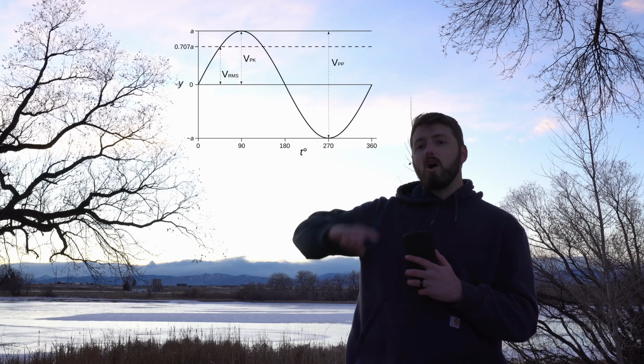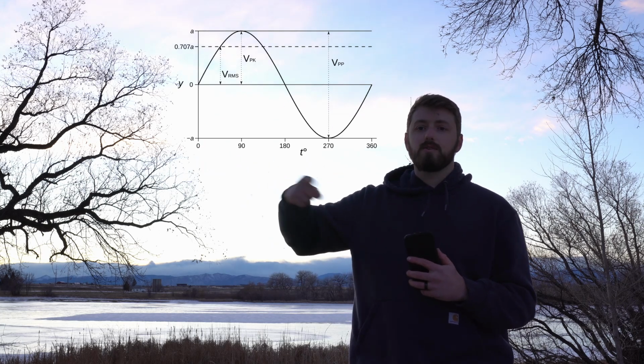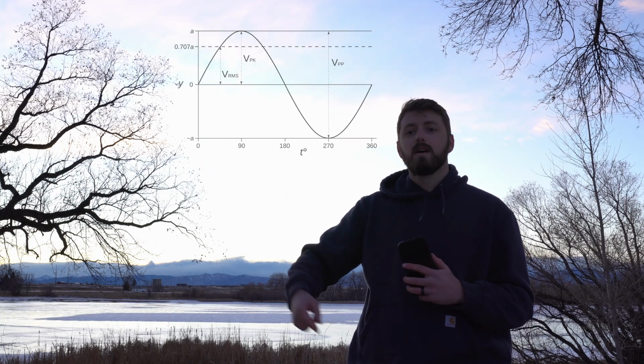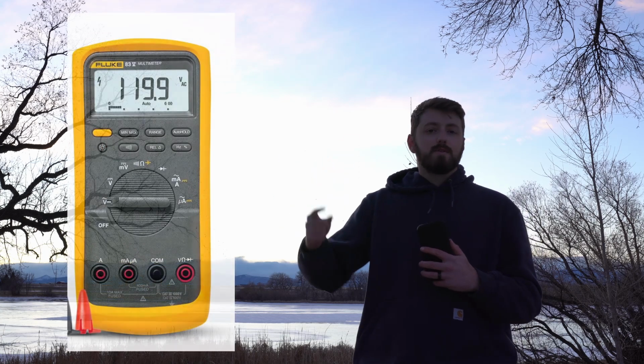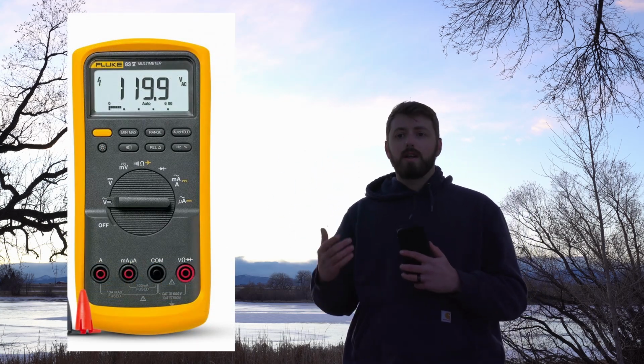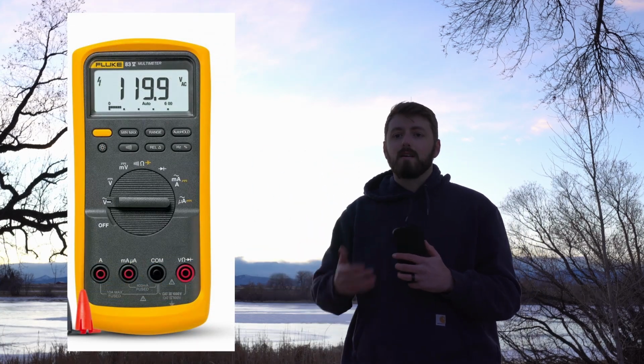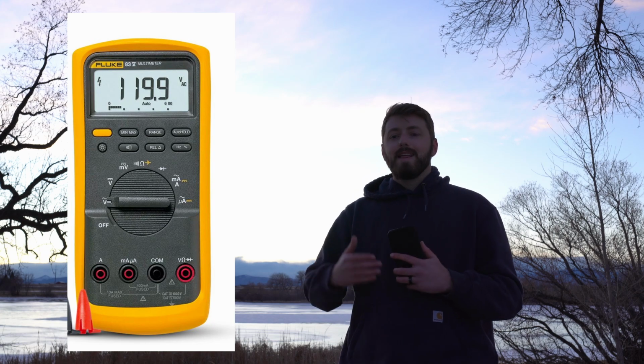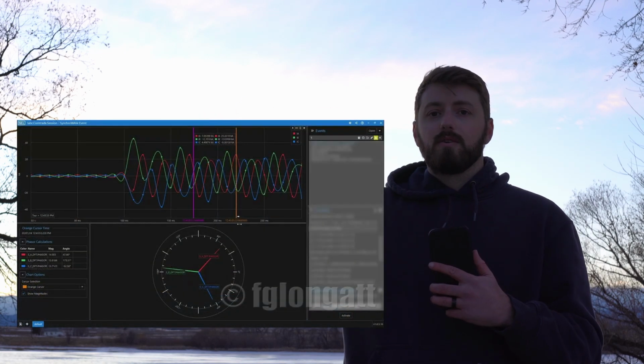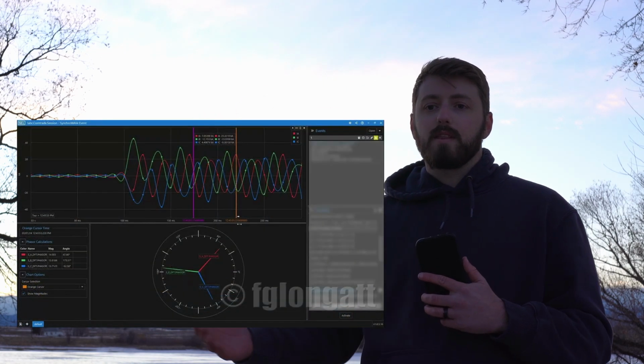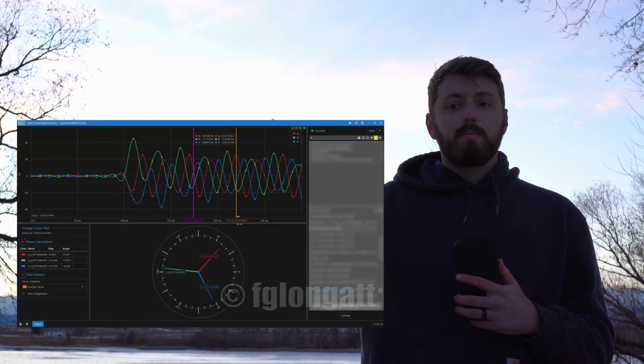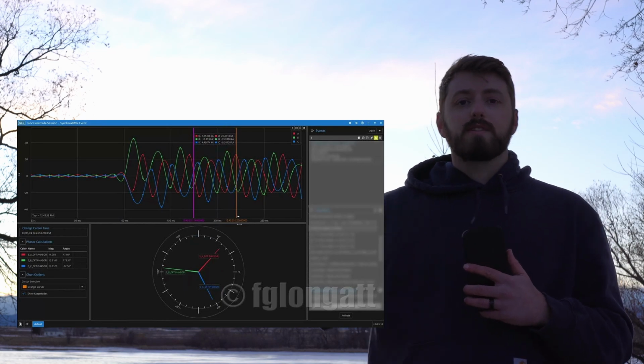Nice. Two key things to remember. The peak voltage is always higher than the RMS voltage, so you can kind of dummy check yourself when you're on your test. And number two, almost every time you see an AC voltage, current, or watts on a multimeter, a relay, or a breaker, that's in RMS quantity, not a peak quantity. If you see on an oscillograph, or like an event analysis on a relay, something similar to that, that might show you the peak quantity, so you need to know the difference and how to get back and forth between the two.